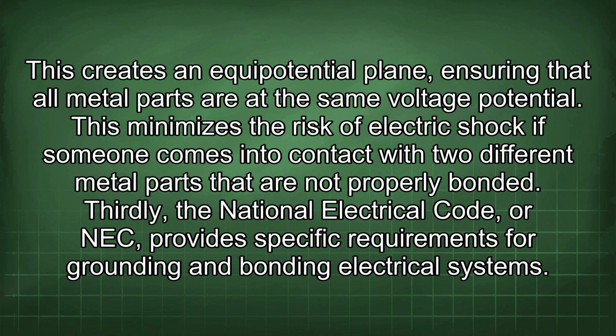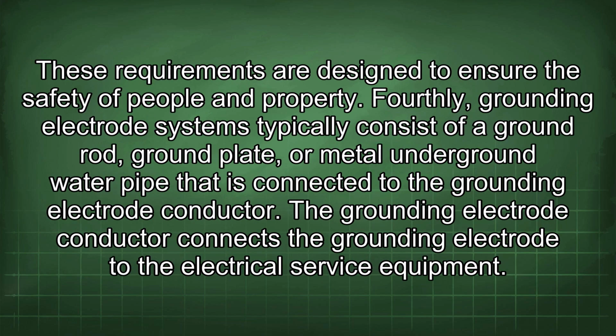properly bonded. Thirdly, the National Electrical Code, or NEC, provides specific requirements for grounding and bonding electrical systems. These requirements are designed to ensure the safety of people and property. Fourthly, grounding electrode systems typically consist of a ground rod, ground plate, or metal underground water pipe that is connected to the grounding electrode conductor. The grounding electrode conductor connects the grounding electrode to the electrical service equipment.